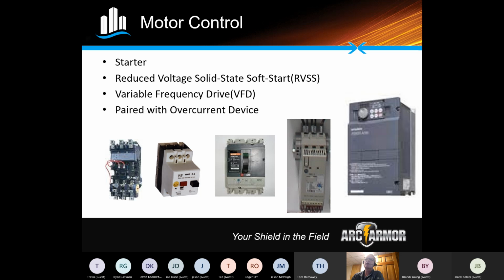This is what a NEMA starter looks like, right here on the left-hand side where I'm running my mouse. Right next to that is also a starter. It's actually a contactor, but it is an IEC type. IEC is more prevalent in Europe. It's smaller scale. What we're starting to see here more in the States is a combination of these two, IEC rated and NEMA rated starters. So, smaller footprint, not as clunky as the NEMA type starters, but that is what we're calling a full voltage non-reversing, or another term is an across-the-line type starter.